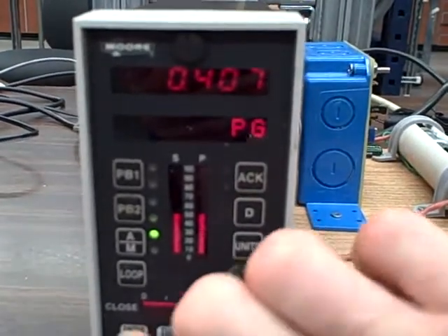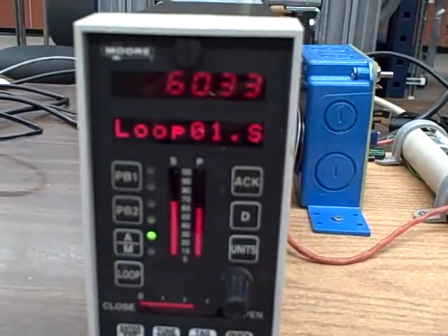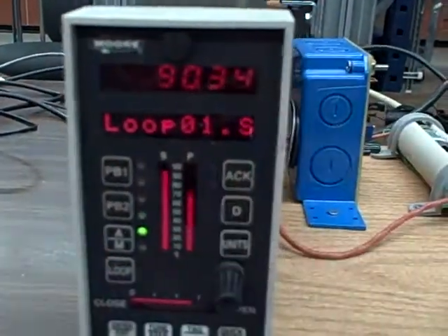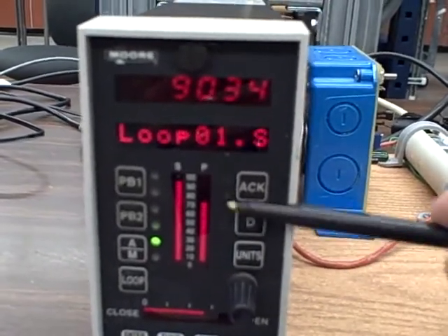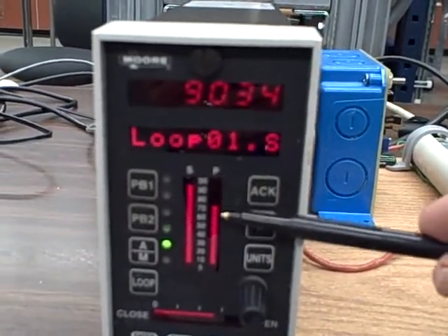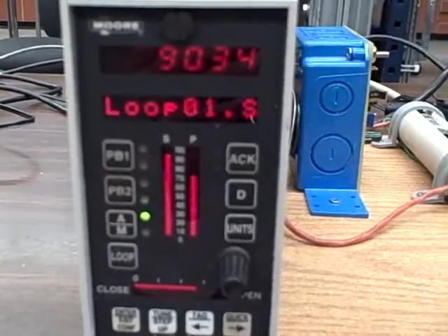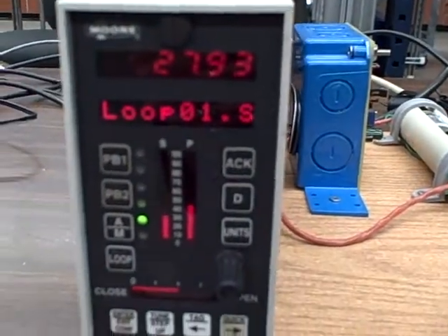Now I can exit out of that display, go back to set point. I'll raise the set point. You'll notice the motor speed does jump up without oscillating. However, now we have quite a bit of offset right here. Notice the amount of offset between set point and process variable. We're not exactly matching set point as we would desire to be. And that's a direct function of having lowered the gain.